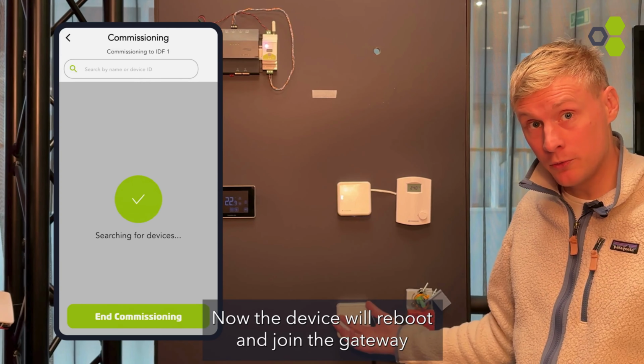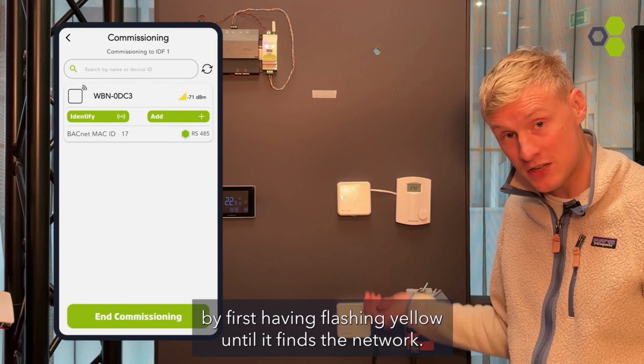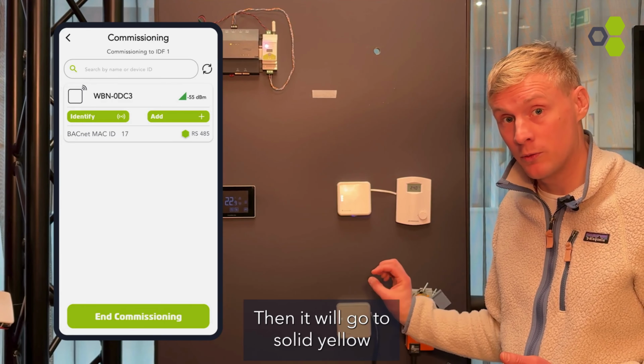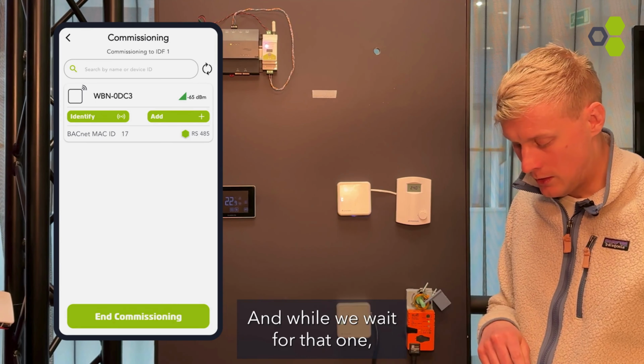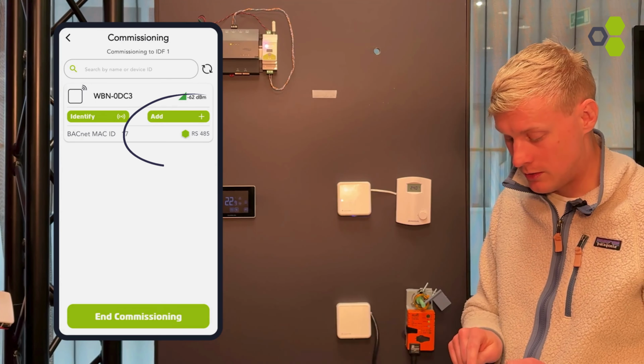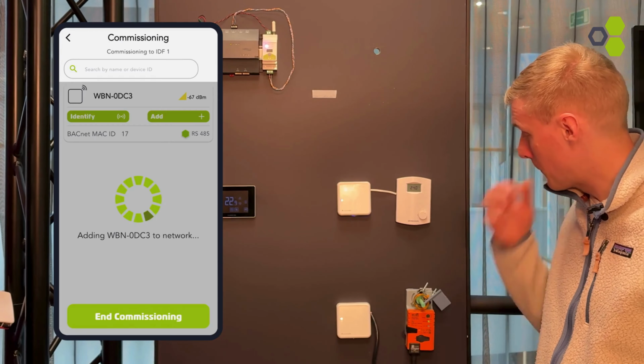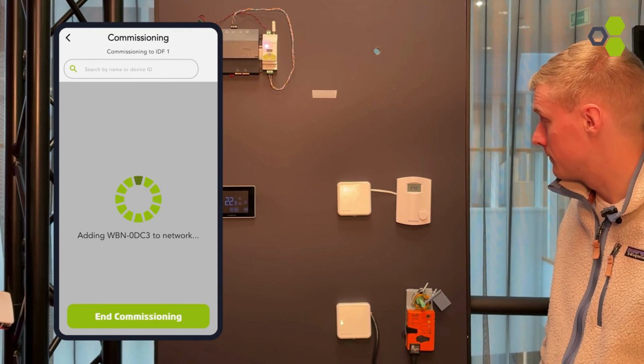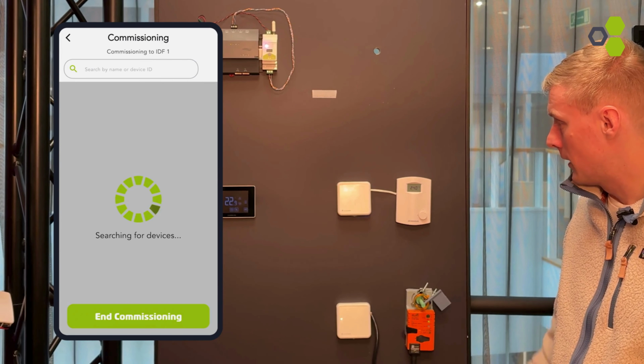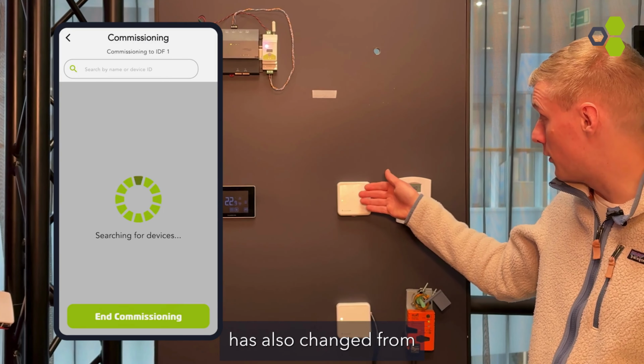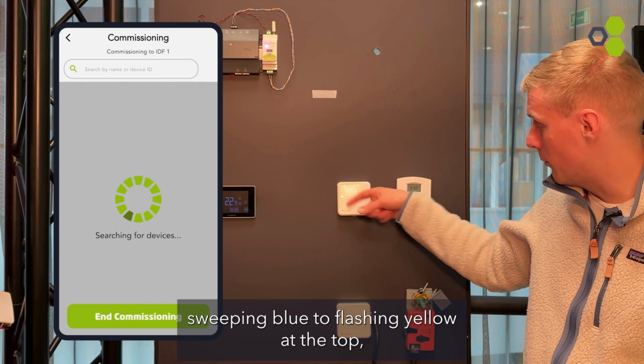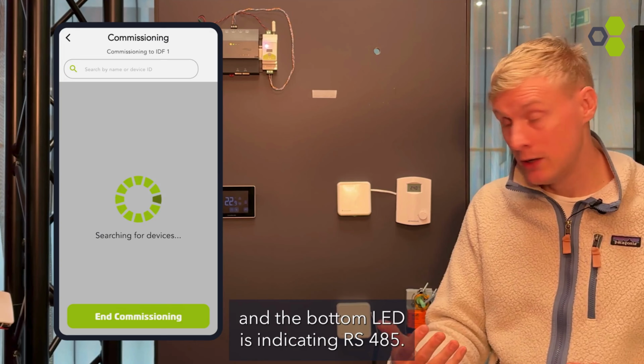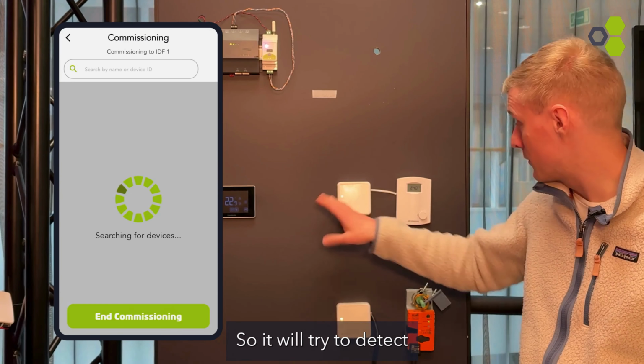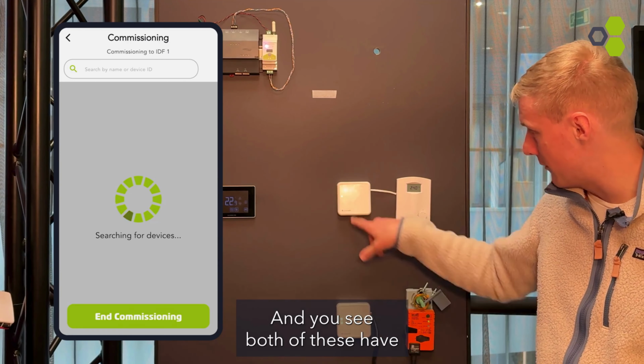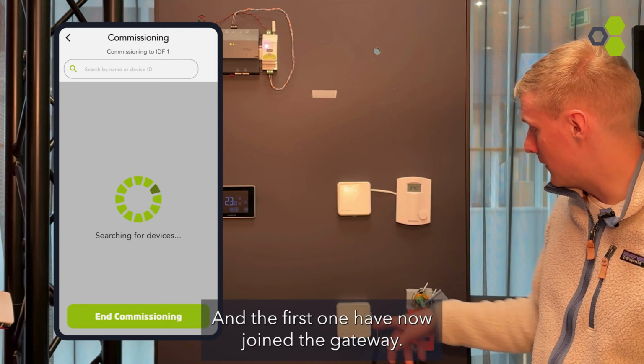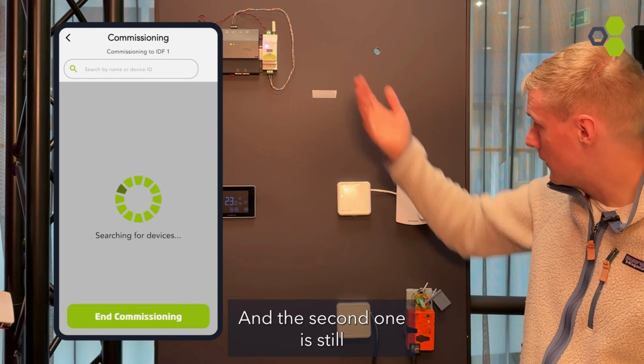Now the device will reboot and join the gateway by first having flashing yellow until it finds the network, then it will go to solid yellow on the top LED. And while we wait for that one, we can commission the other one. And now you see that the second one has also changed from sweeping blue to flashing yellow at the top. And the bottom LED is indicating RS485. In this case, I've set it to auto baud, so it will try to detect the baud rate of the other device. And you see both of these have found their corresponding BACnet device. And the first one has now joined the gateway, and the second one is still trying to join the network.